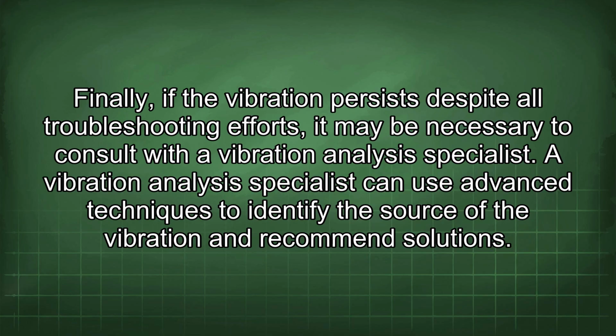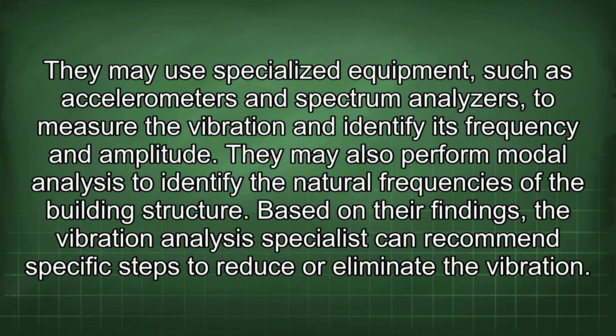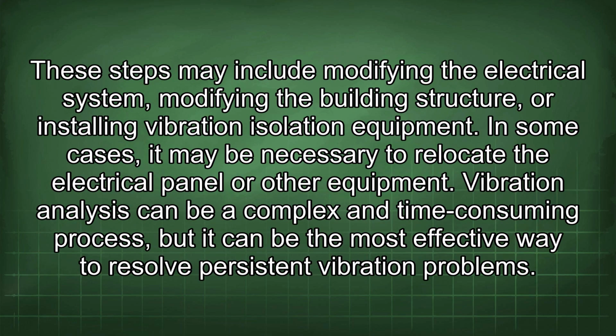Finally, if the vibration persists despite all troubleshooting efforts, it may be necessary to consult with a vibration analysis specialist. A vibration analysis specialist can use advanced techniques to identify the source of the vibration and recommend solutions. They may use specialized equipment, such as accelerometers and spectrum analyzers, to measure the vibration and identify its frequency and amplitude. They may also perform modal analysis to identify the natural frequencies of the building structure. Based on their findings, the vibration analysis specialist can recommend specific steps to reduce or eliminate the vibration. These steps may include modifying the electrical system, modifying the building structure, or installing vibration isolation equipment.